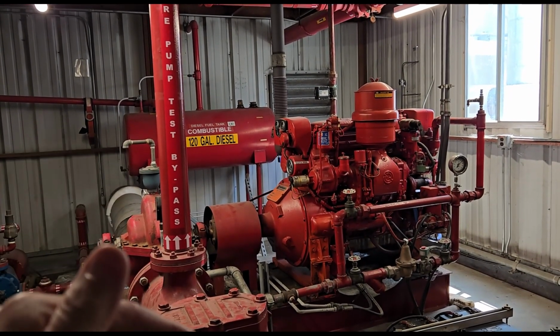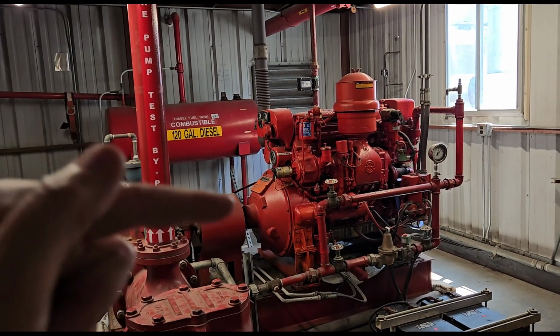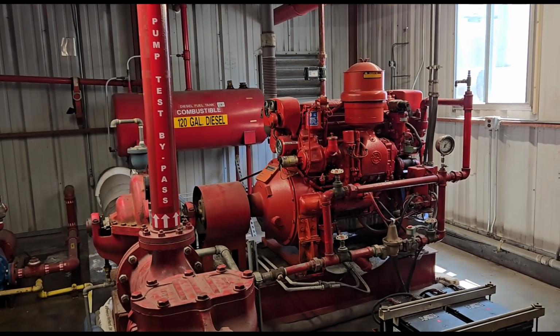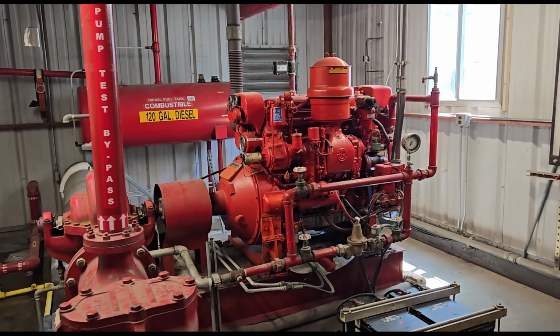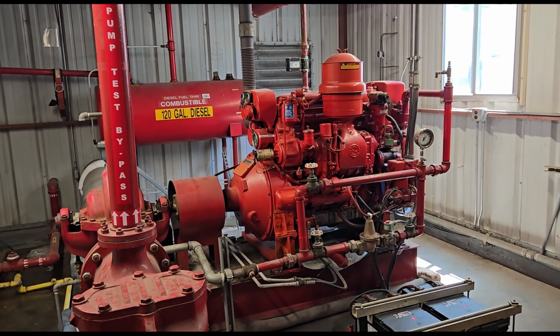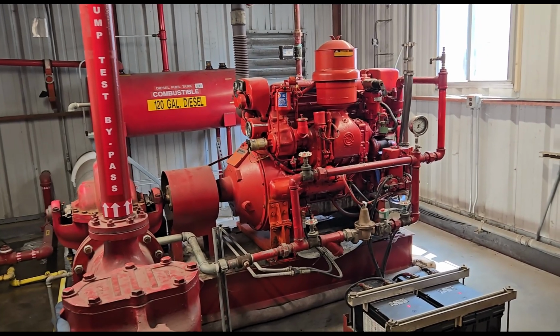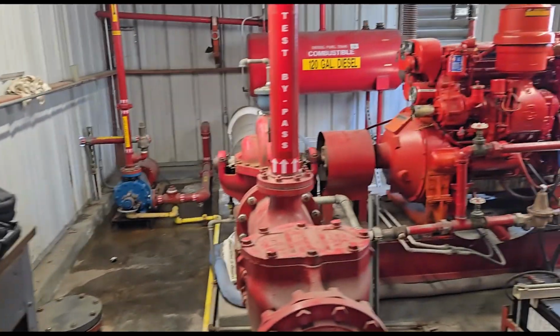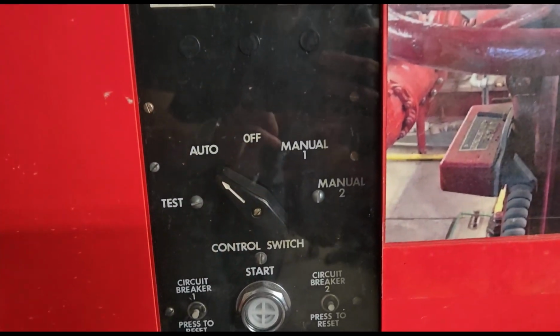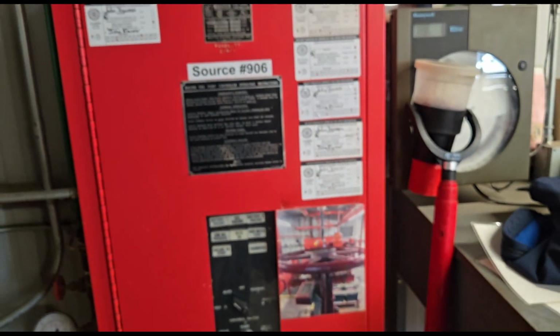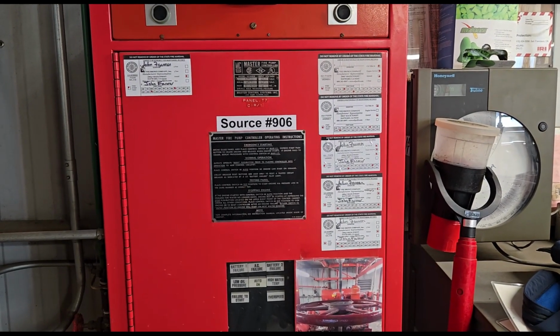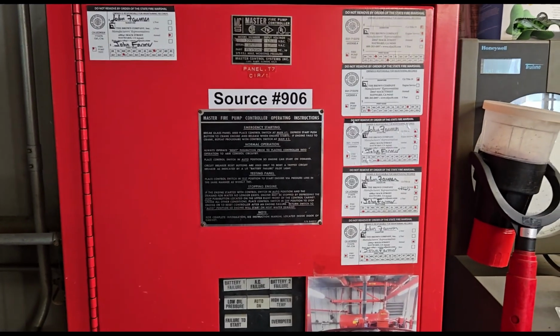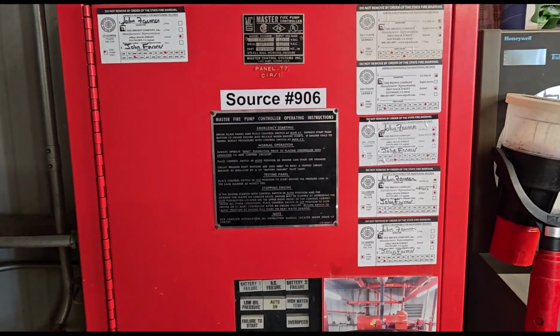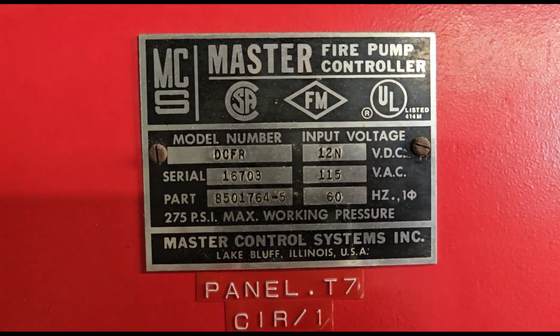If we had a sprinkler team here, they would be doing all the pump testing for us. They would be running it and supervising it while we do the flow testing. But like me, I'm just the alarm technician, so I'm testing all the alarm devices. This client has a separate contractor for the sprinkler system, so they do it at a different time. Since they don't want to sync us up at the same time, we just bypass the pump. We run everything off the jockey pump, and we just use our little turn dial to switch it off. So you can see it's back on auto. Kind of an exhaustive process, but just to show how it's done, to be on the safe side. So anyway, that is how you bypass or turn off the diesel fire pump for the Master Control Systems diesel fire pump controller.